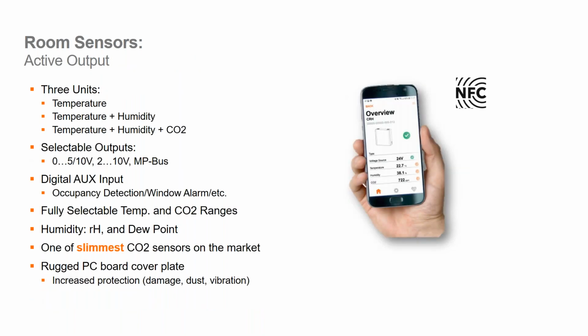When we look at our active output sensors, they're a little more flexible. So you have a temperature, a temp humidity, and of course a temp humidity and CO2 output. These are all active, so these are going to be all voltage style outputs, or they can communicate via our MP bus to specific devices. But those outputs are adjustable, as you can see, using that Belimo Assistant and an iPhone or Android. So you can field configure those. You don't have to connect to the controller to do it. You can simply connect to the wall module to change the wall module's output.